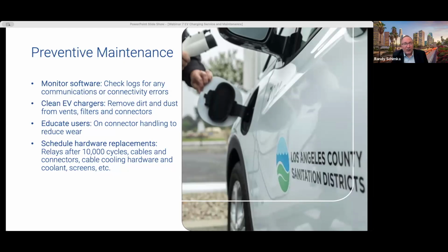Finally, schedule hardware replacements. Plan to swap out relays, contactors, and other parts that typically see wear after about 10,000 charging cycles, or according to the manufacturer's recommended intervals. Other parts that may also need to be replaced periodically include cables and connectors, cable cooling systems and coolant, and screens. Proactive replacements prevent unexpected failures and help to keep chargers more reliable.